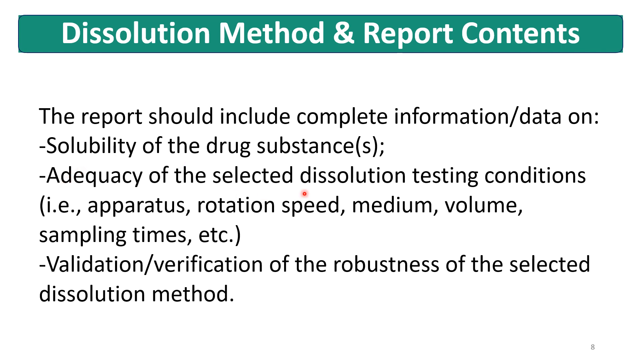The adequacy of the selected Dissolution testing conditions will involve the selection of apparatus — whether USP 1, USP 2, USP 3, or USP 4 — which must be clearly stated with justification. Data comparing apparatus 1 and 2 in parallel is typically provided, with justification for why a particular apparatus was selected. Similarly, the rotation speed, medium, media volume — whether 500 ml, 600 ml, 900 ml, or 1000 ml — and the sampling times are determined and documented. Validation or verification of the robustness of the selected Dissolution Method is also required in the report.